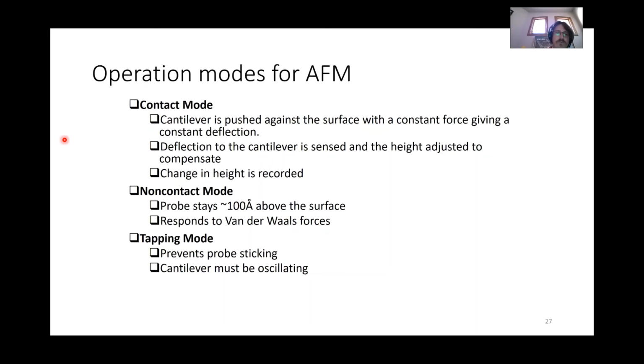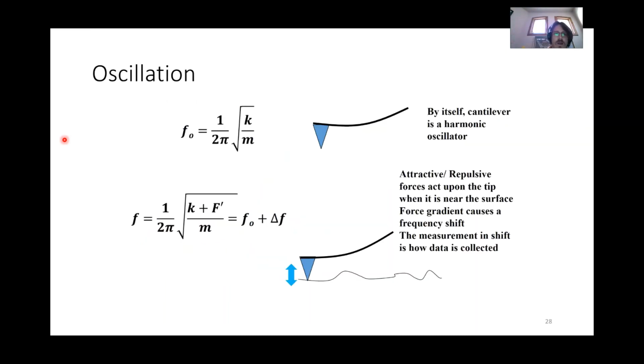Tapping mode prevents probe sticking, and so it's actually oscillating. So you're oscillating this probe, so it's a harmonic oscillator. By itself, and I won't get too much into these, the cantilever is a harmonic oscillator. Attractive and repulsive forces are acting upon the tip when it's near the surface, and there's a gradient to this force, and it's causing the frequency shift. And the measurement of that shift is how data is collected, basically. And I may go into more detail on this. I may not, just because we have a lot of topics. But the cantilever is a harmonic oscillator.